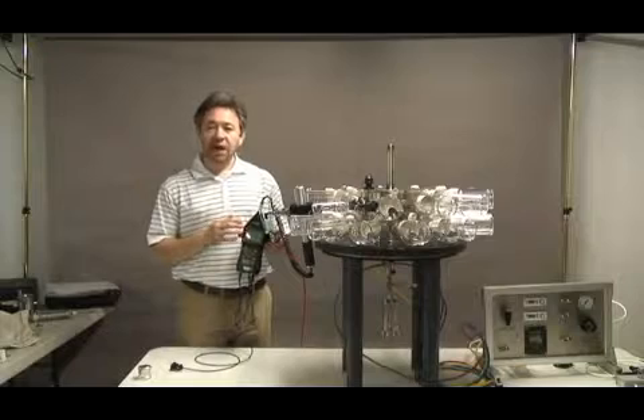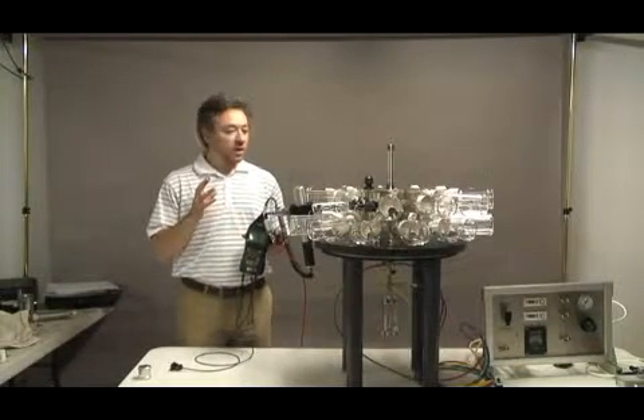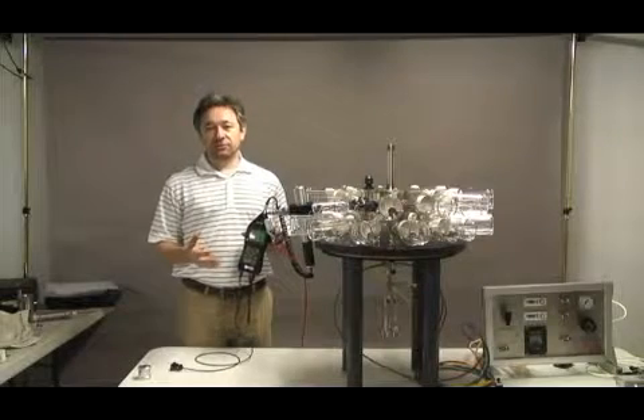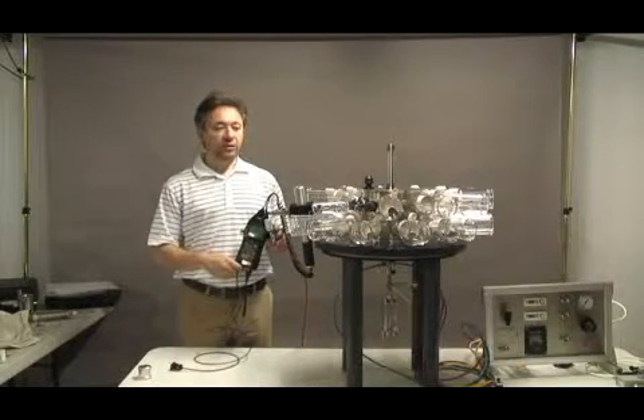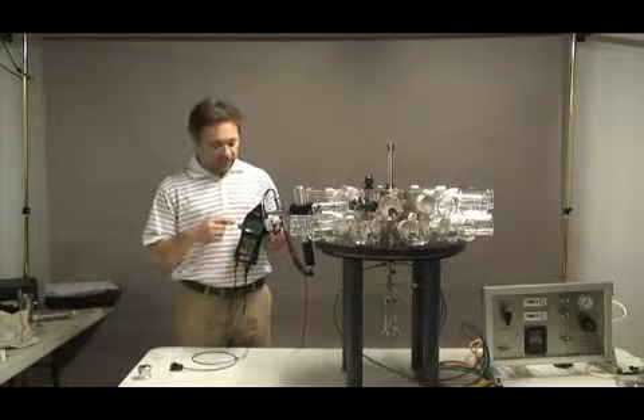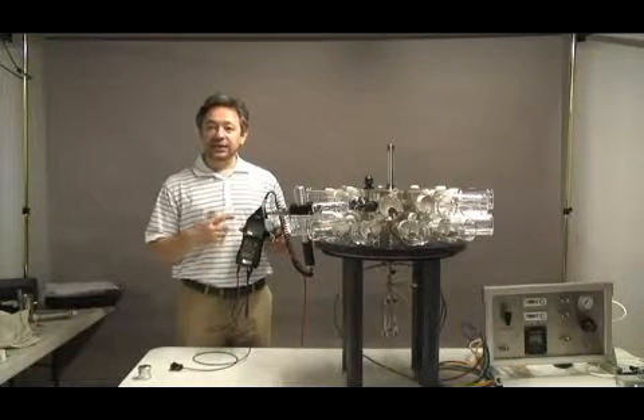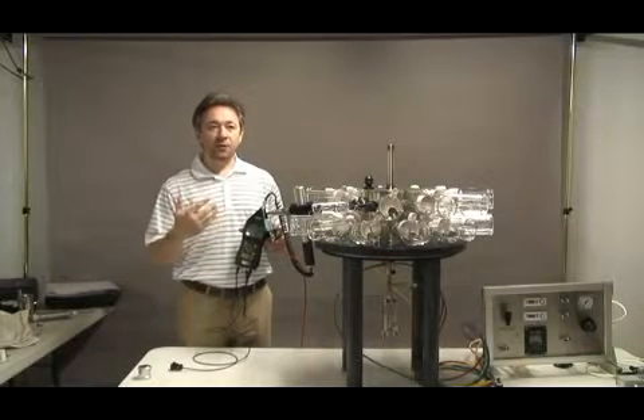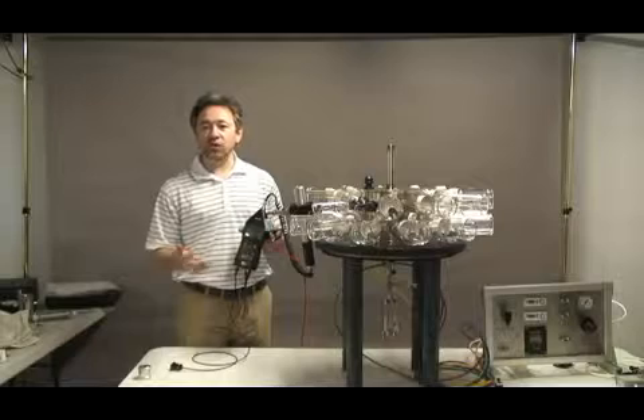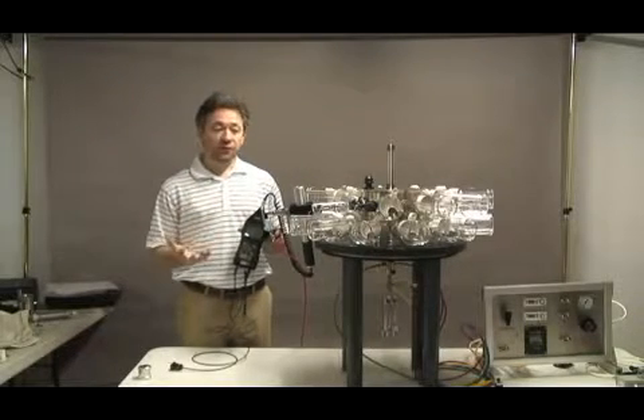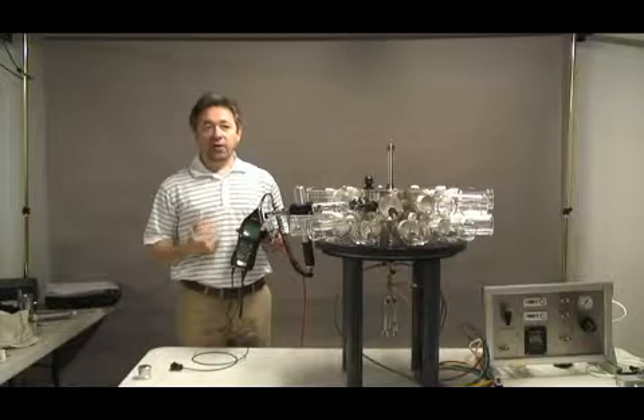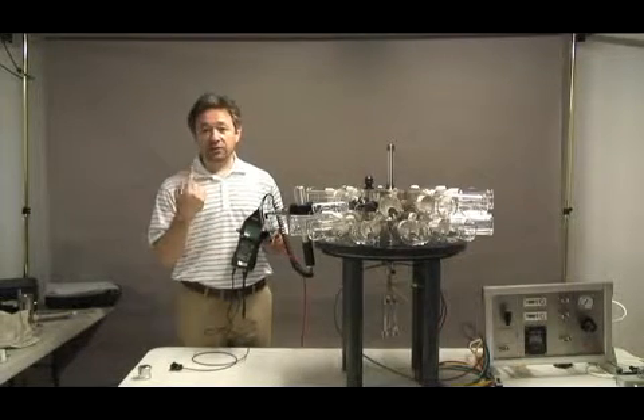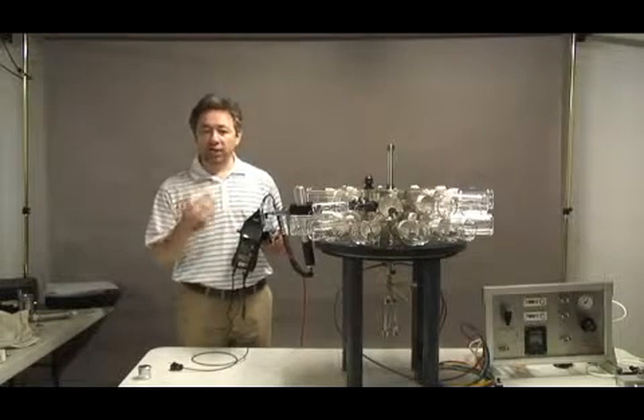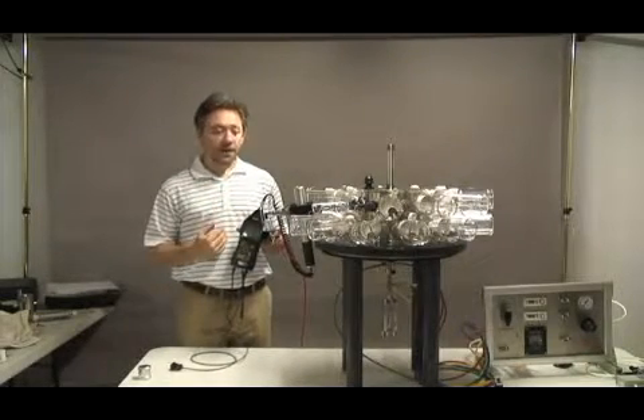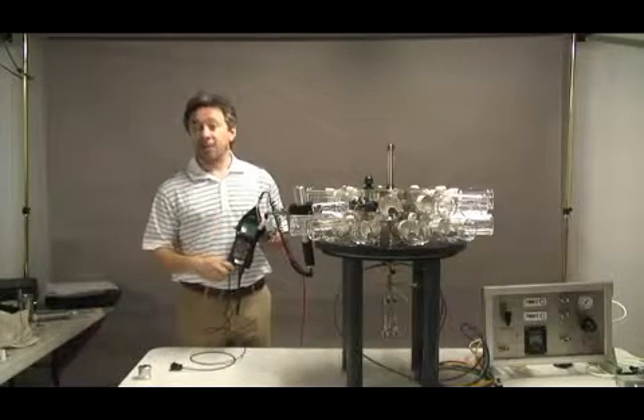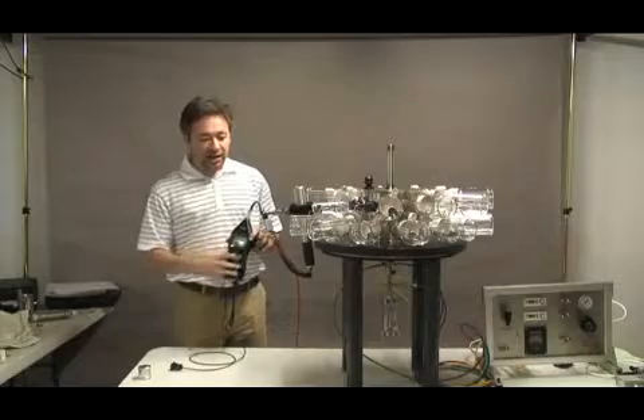The probe comes calibrated with Arizona road dust. So for any new powder or aerosol or liquid aerosol that you're going to use the system with, the probe needs to be calibrated for the specific aerosol, the scattering capabilities of the particular aerosol. So if Arizona road dust is calibration factor 1, different dusts or liquid aerosols will have a different scattering capability.